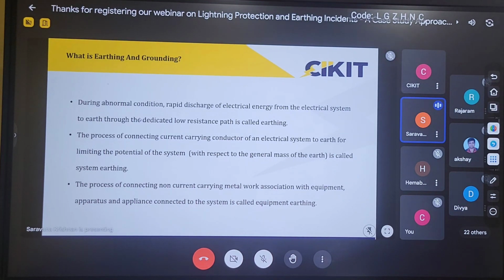If I'm connecting this earthing to the neutral of a transformer, it will be considered as system earthing, because the neutral is a live part. So when connecting the current carrying conductor, it will be considered system earthing. So if I'm providing system earthing, the fault current has to be considered. And if the fault conductor sizing is not proper, the conductor may melt and break. So we have to select the conductors accordingly.